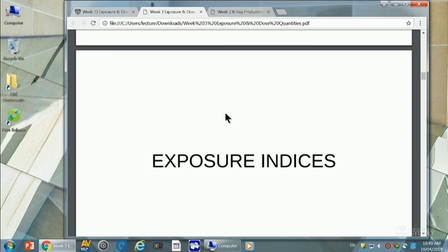So with film, it was easy. If someone X-rayed a patient and it came out too black, you'd see the image within half a second: you've overdosed that patient. If it's too light, you haven't given enough. With digital, we no longer have that control. What an exposure index does is give you a number every time you X-ray someone. You see some sort of number on the monitor which indicates the level of exposure given. I'm going to give you a lecture on how that works. It's really quite a straightforward procedure.